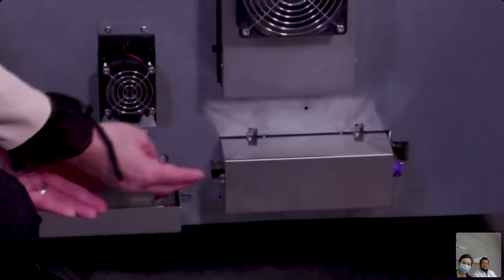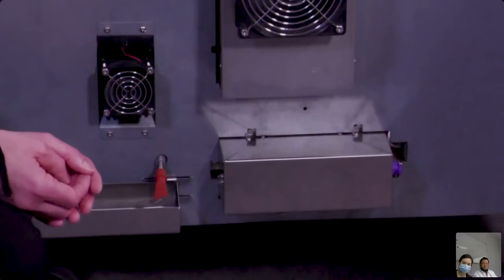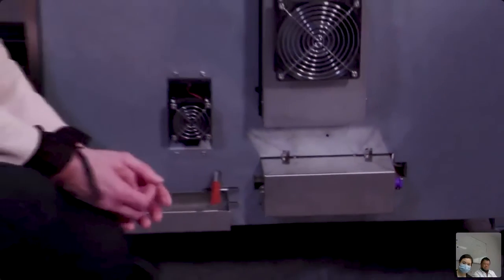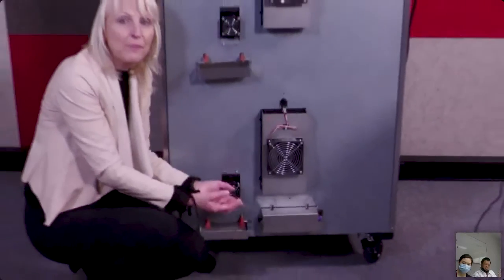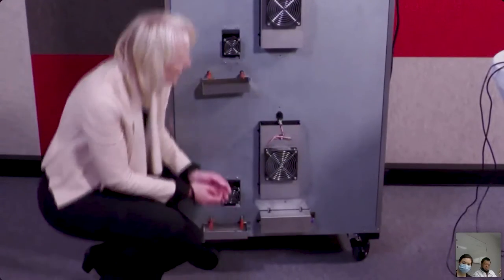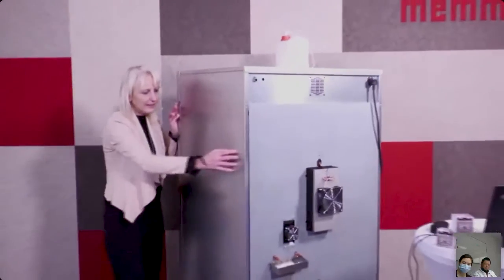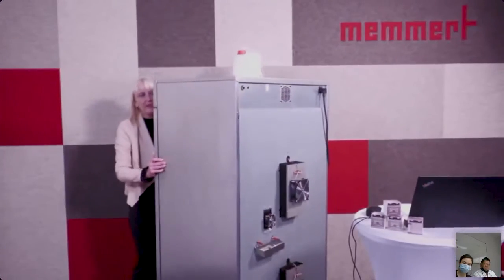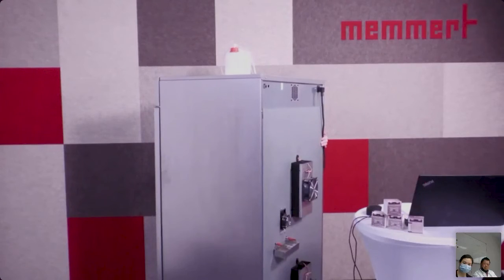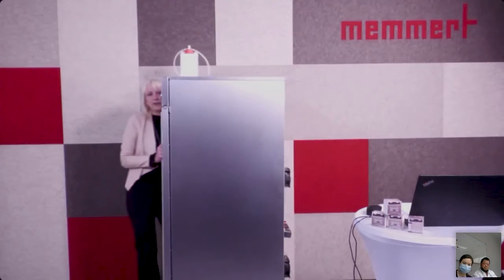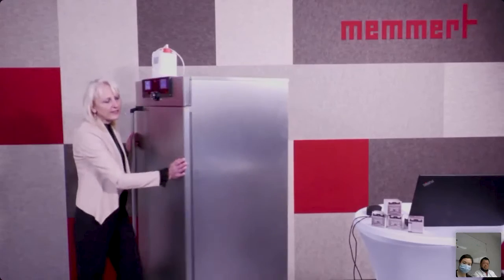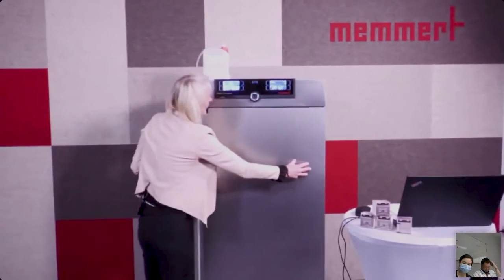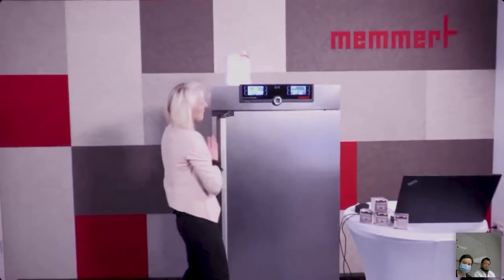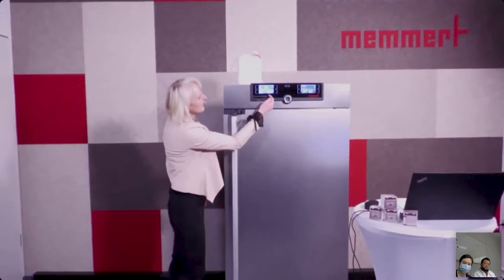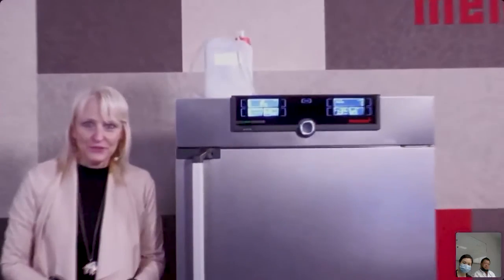Micrometering pump, which is also a new feature, which refers to the humidification of the unit, and which means mostly precise humidification and the fastest humidification. That is also considered on our constant climate chamber. And as you can see, this constant climate chamber does not have any compressor. So this constant climate chamber is based on this Peltier technology, which is our new advanced technology, which is used by Memmert. Our new model, advanced eco Peltier technology.